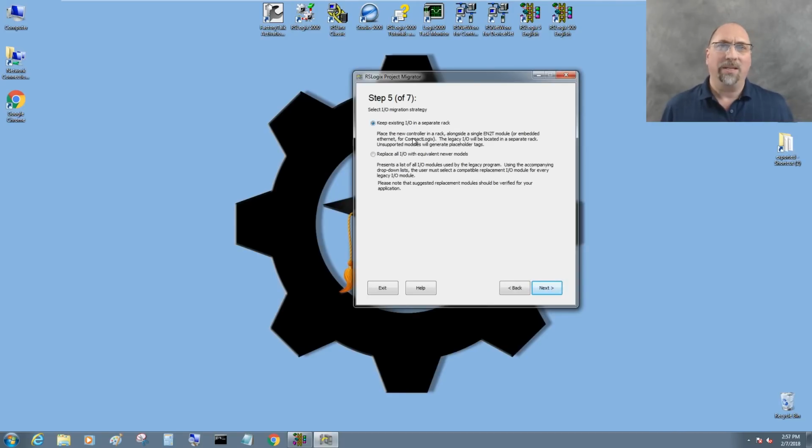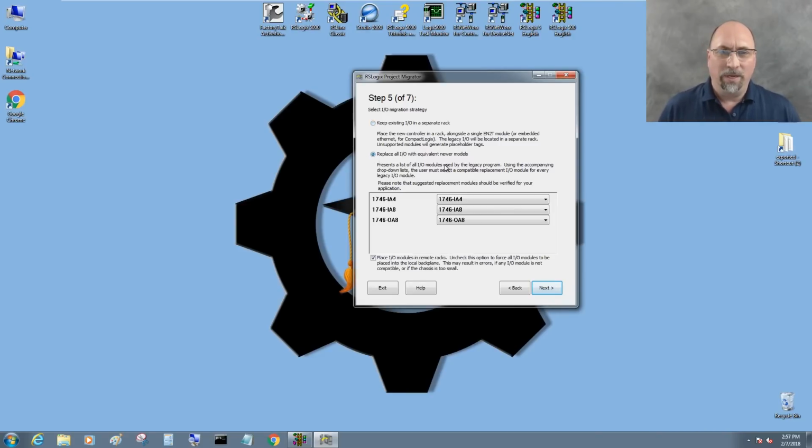Now here it's asking, and this is a good option if you have a SLC 500 rack and you don't want to unwire the whole thing, it's asking, hey, do you want to keep that existing I/O? I don't. I'm replacing this old SLC with a CompactLogix. So let me go here and say replace all the I/O.